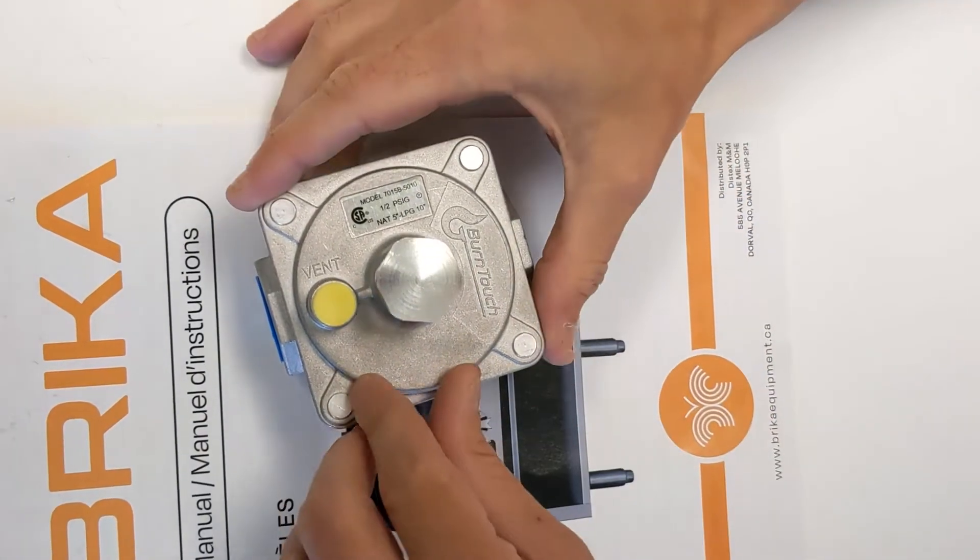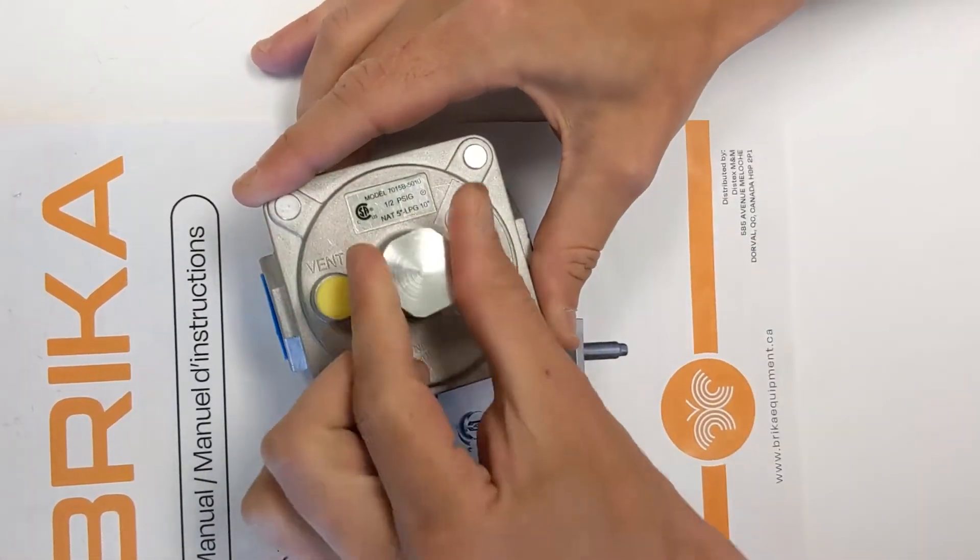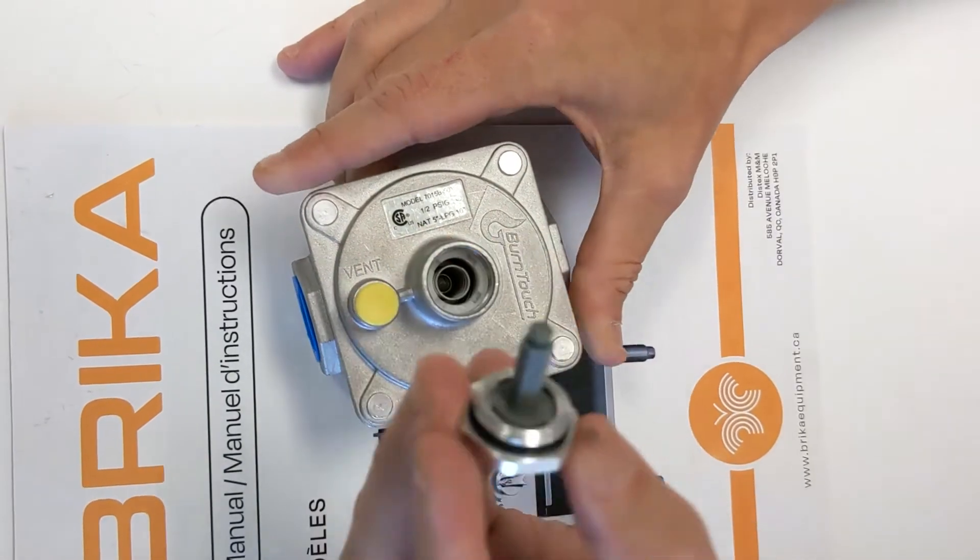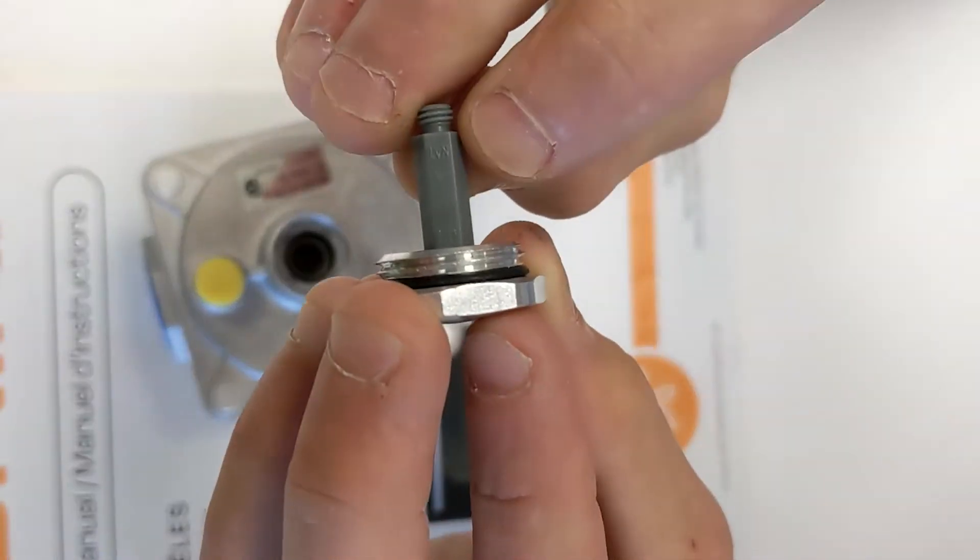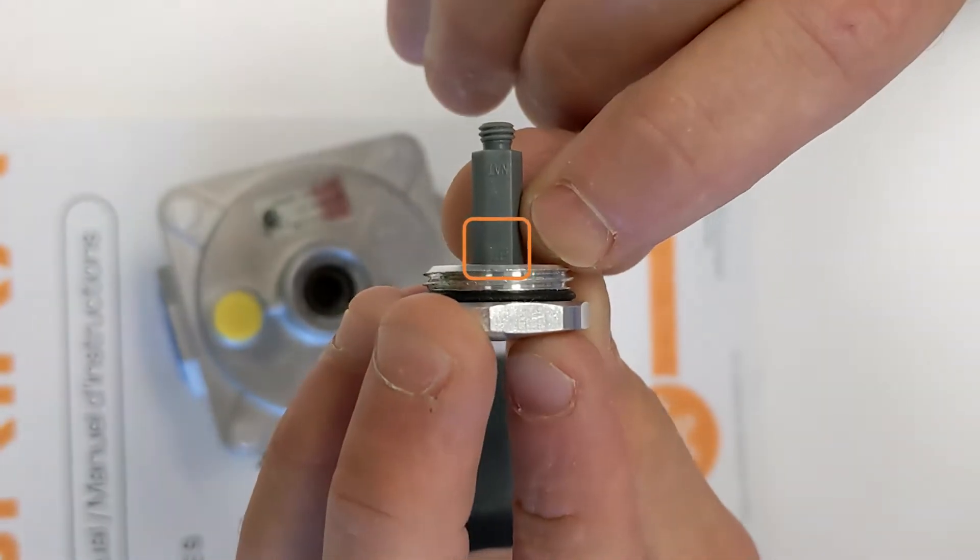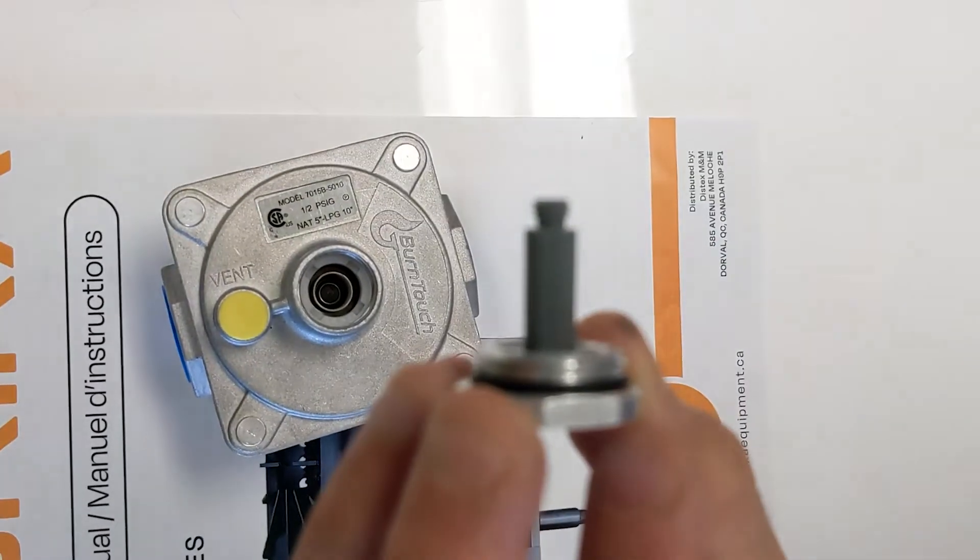This is how to convert the gas regulator. First, we're going to remove this cap by unscrewing. And here we have a stem on which we see natural and LP. Right now, it's set for natural gas.